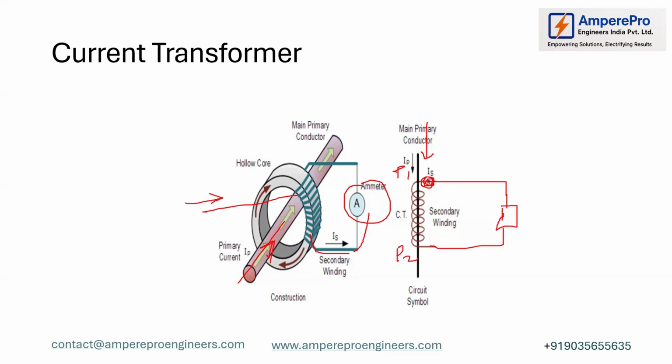When there is a mismatch, if it is reversed, there is a possibility of nuisance trip in the relay. In that case, you need to do the root cause analysis.